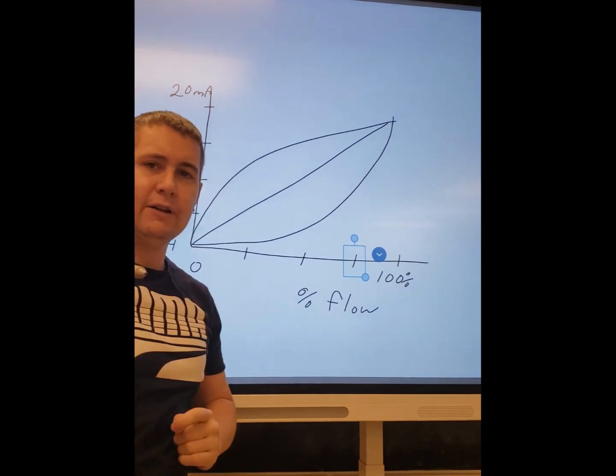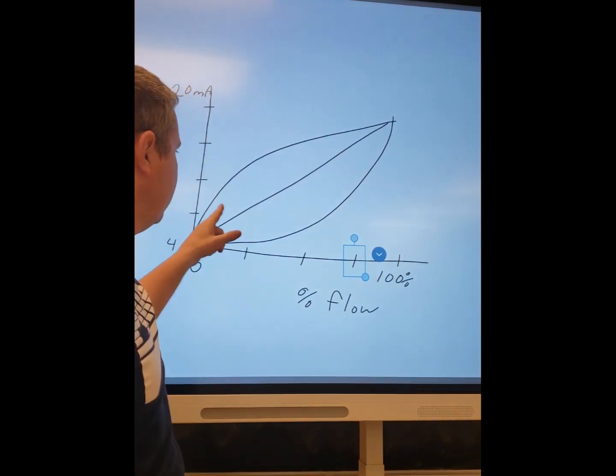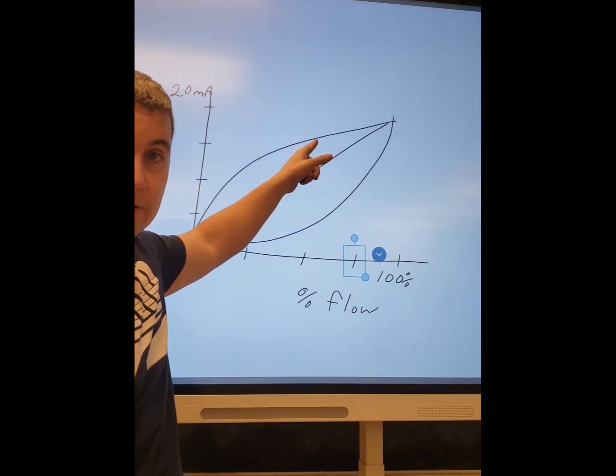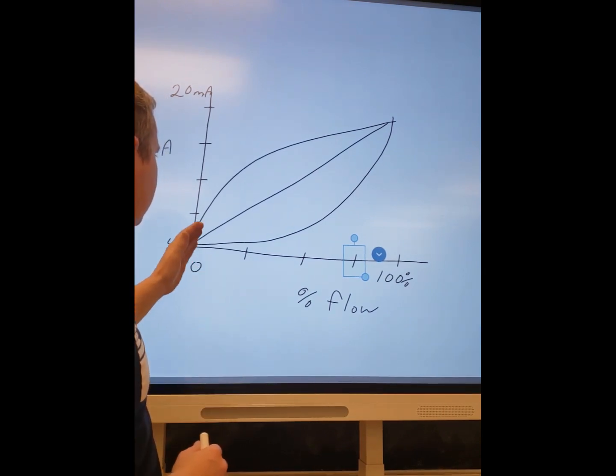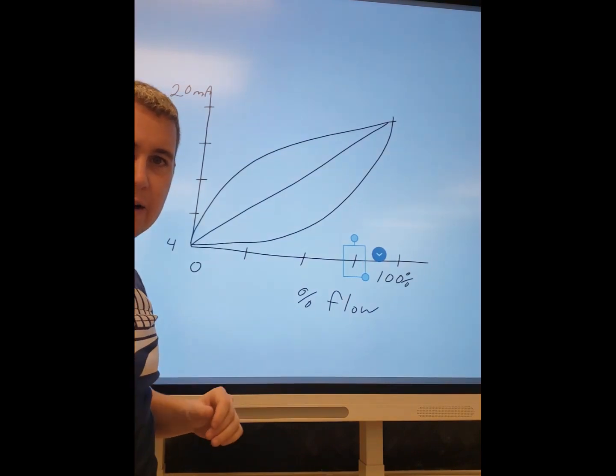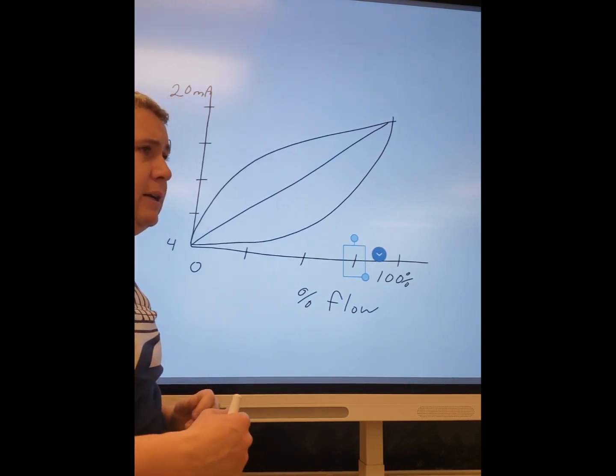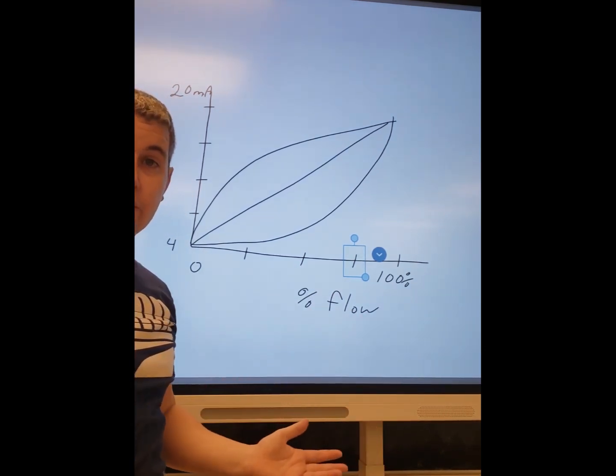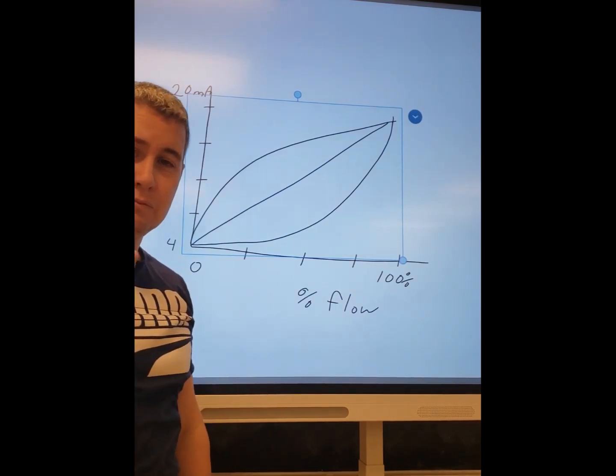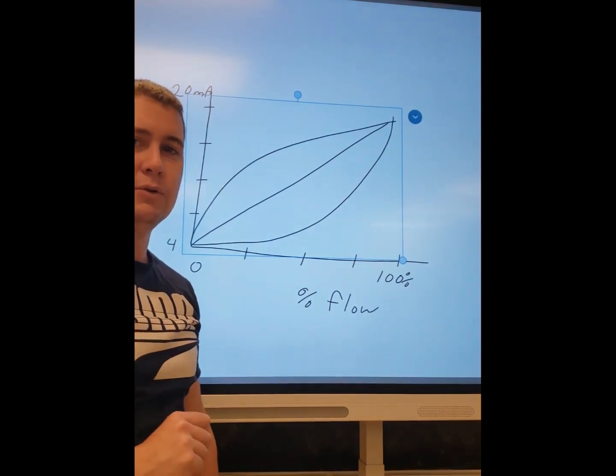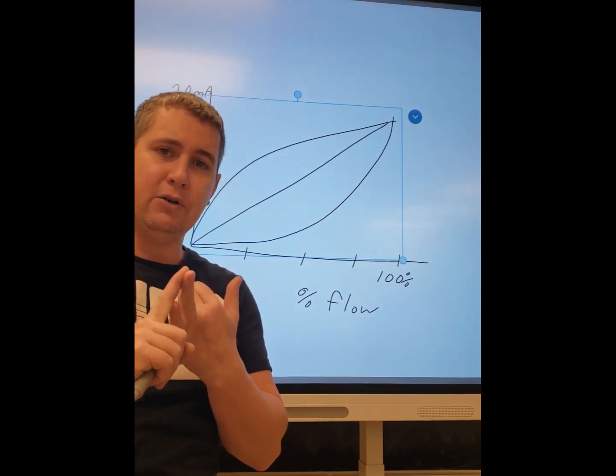Now why is this important? Because if you leave a transmitter in a square root function and you actually have a linear input like level, you will end up getting a square rooted output. So if you go to look at the level of a tank and you see that your output has this wild curve on it, you know that your square root extractor function on the transmitter is on. If you're doing flow like differential flow and you get this curve as your output, you know that you have your linear function on and you need to square root it. When you're doing flow you need to square root, when you are doing level you need to keep your output on a linear function.